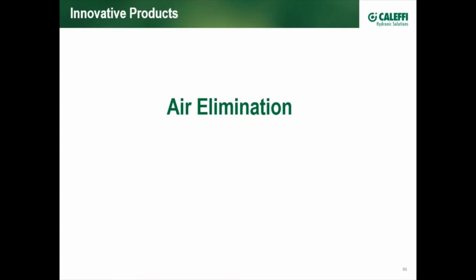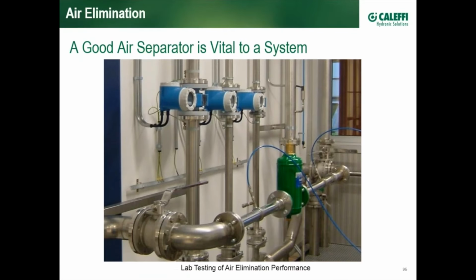Moving on, air elimination. We mentioned magnetite formed by oxygen, right? So it's important for many reasons for air not to enter into a system, or if it does, to automatically rid itself. Caleffi does a lot of air separators. We also do a lot of testing, both of Caleffi and of competitors. Here's a Caleffi unit where we're measuring the efficiency.